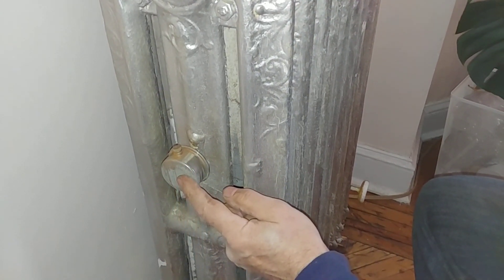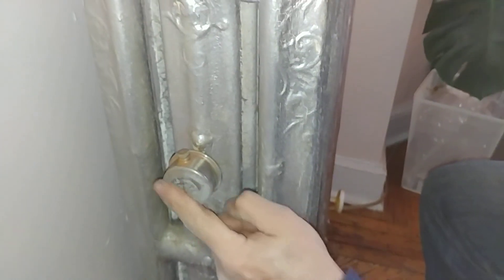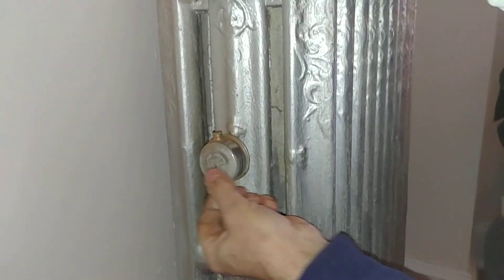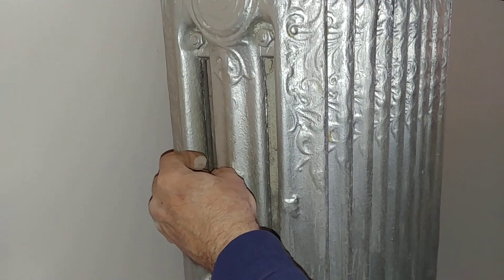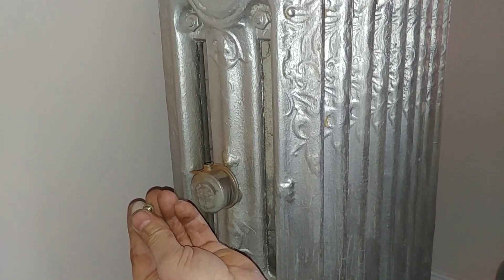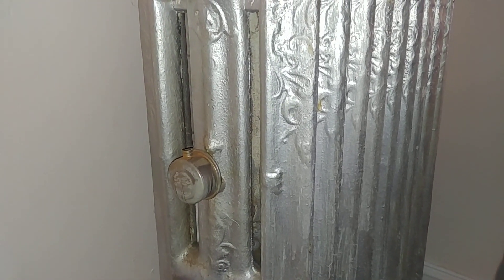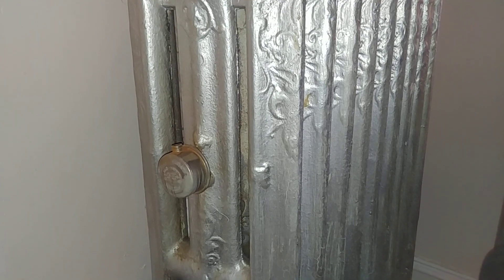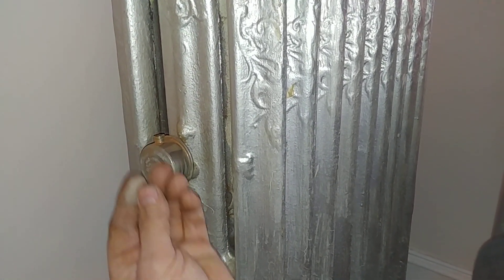What we're going to do is we're going to try to remove this Maid-O'-Mist. This is a Maid-O'-Mist, and one advantage of the Maid-O'-Mist is the adjustable orifices. This is a C, which is fairly large. The main issue is the main vents downstairs are not big enough, so in order to compensate for that, they put these large holes in there.